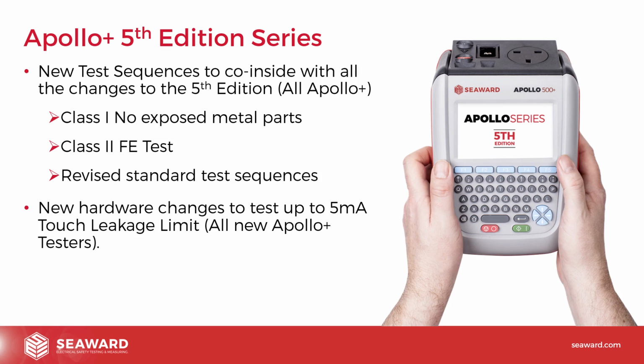So the only difference really, if you're an existing Apollo user and you put on the 5th edition firmware, the only difference is your test sequences will only allow you to measure up to 3.5 milliamps for touch current, whereas obviously now the code of practice says it's 5 milliamps. But considering previously everything was only 0.25 milliamps, quarter of a milliamp, I don't think you're going to come across much equipment that's actually got touch currents greater than 3.5 or that sort of thing. So again, working to the older limits, all we're doing is the older limits are tighter limits, whereas now, obviously, the limits have gone up to 5 milliamps. So really, from that side of things, there's no real safety concerns from that. It's just the fact that the new limits are actually 5 milliamps.